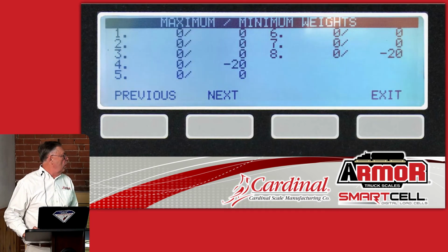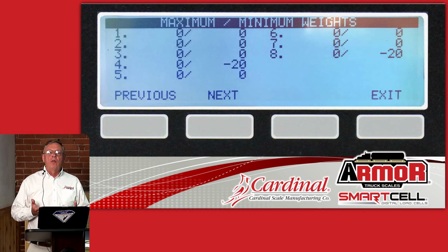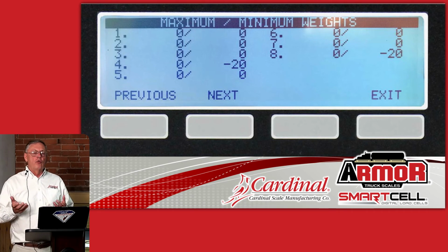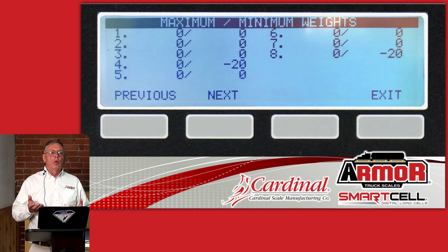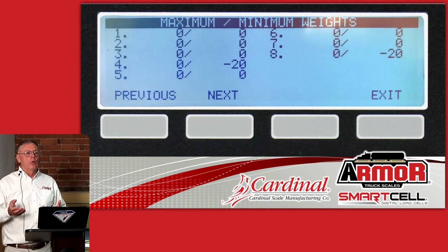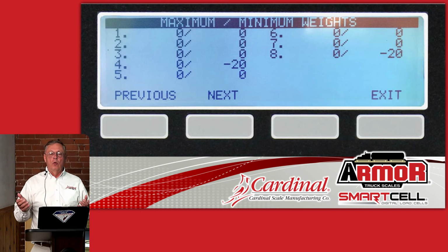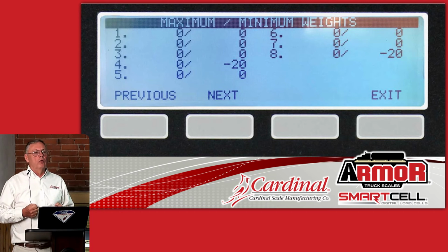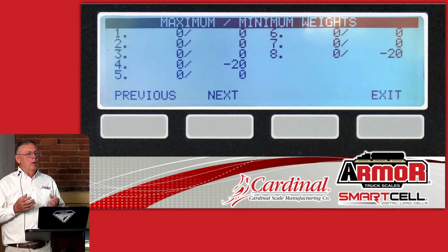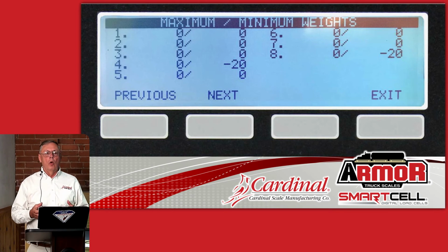Now, the second diagnostic screen. If we have an issue with maybe a load cell that's got a drifting weight for whatever reason, a technician may get a phone call from the end user that says, hey, this scale's drifting all over the place, going nuts on us. On an analog system, sometimes that can take a long, long time to figure out what's going on.